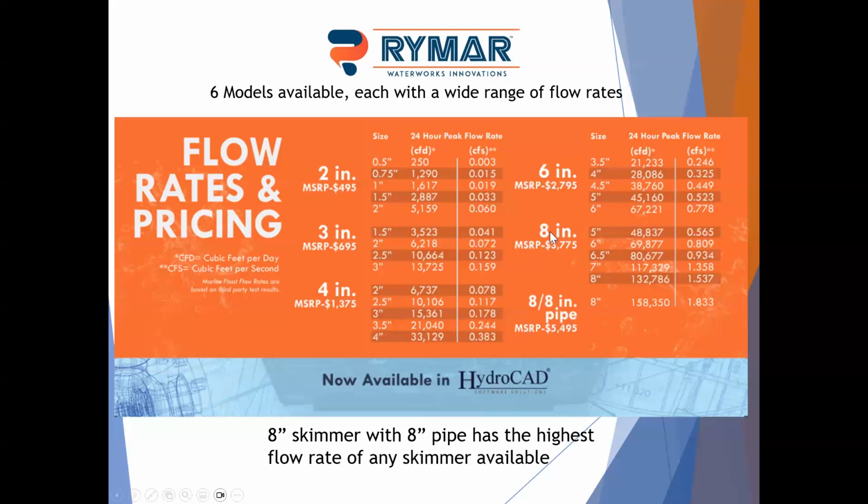Our standard 8 inch uses a 6 inch pipe to connect the 8 inch skimmer to the riser structure. The flow rate there is 1.5 CFS. Most other competitors' flow rate for an 8 inch is around 0.9 to 1 CFS.